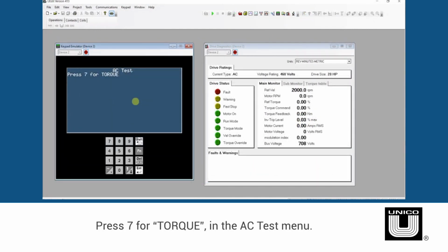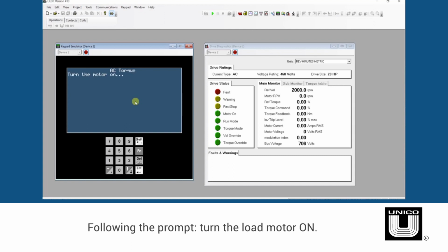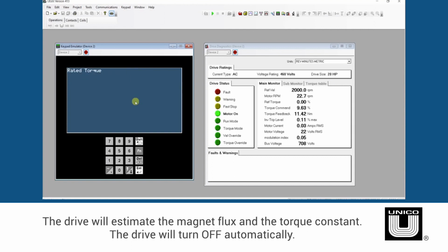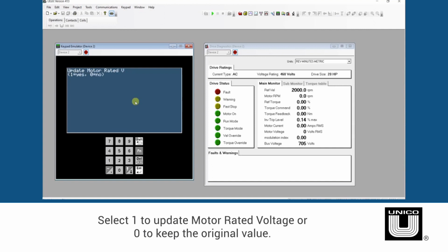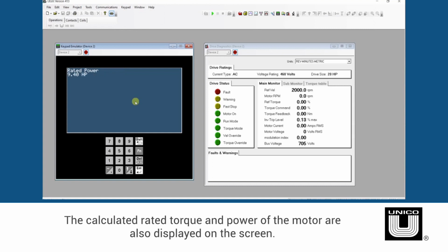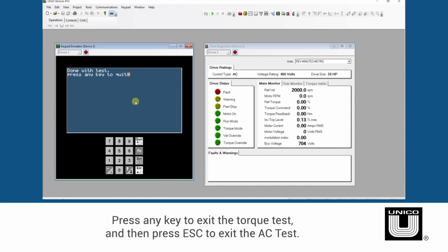Next, select 7 for the torque test. Once the motor is on, the drive will estimate the magnet flux and the torque constant. In addition, the drive will update the motor rated voltage. Select 1 to update or 0 to keep original value. The calculated rated torque and power of the motor is also displayed on the screen. Press any key to exit the torque test and then select Escape to exit the AC test.